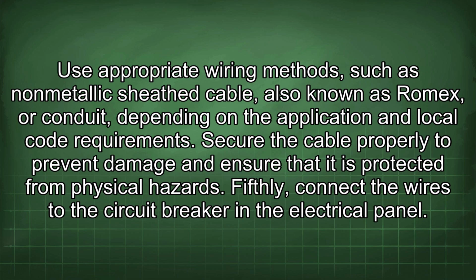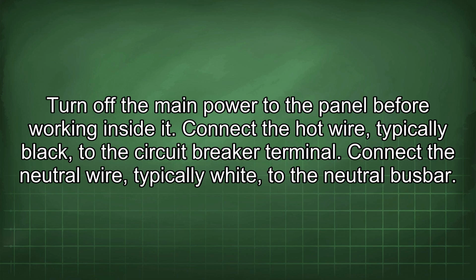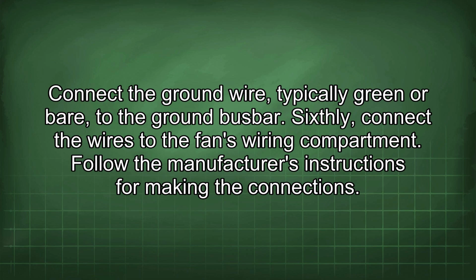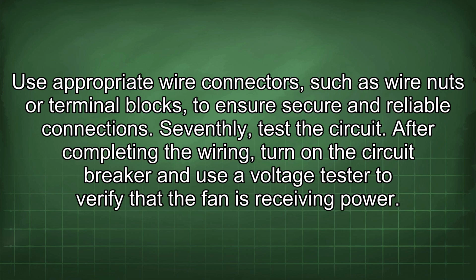Fifthly, connect the wires to the circuit breaker in the electrical panel. Turn off the main power to the panel before working inside it. Connect the hot wire, typically black, to the circuit breaker terminal. Connect the neutral wire, typically white, to the neutral bus bar. Connect the ground wire, typically green or bare, to the ground bus bar. Sixthly, connect the wires to the fan's wiring compartment. Follow the manufacturer's instructions for making the connections. Use appropriate wire connectors, such as wire nuts or terminal blocks, to ensure secure and reliable connections.